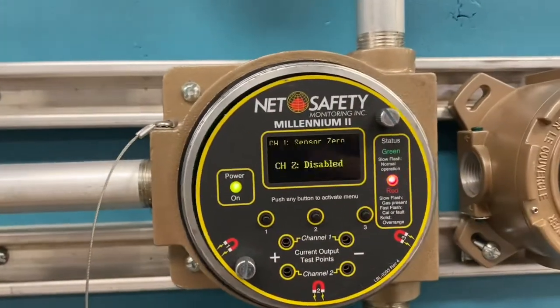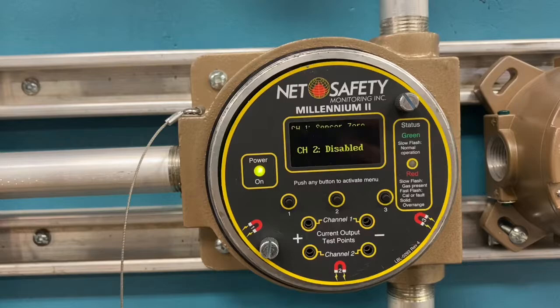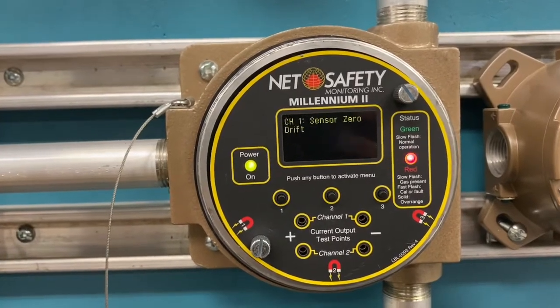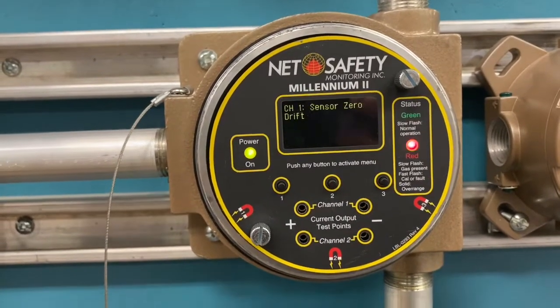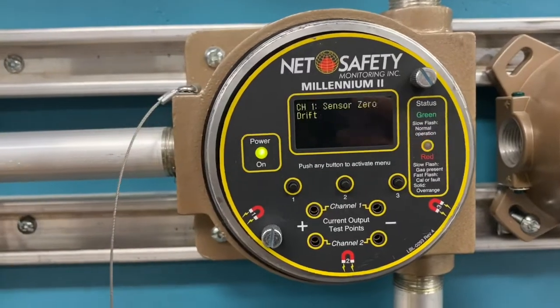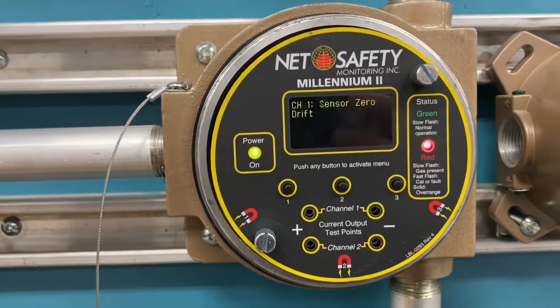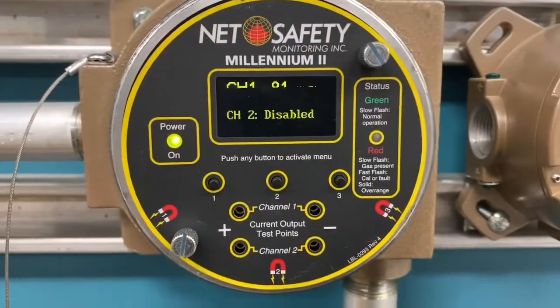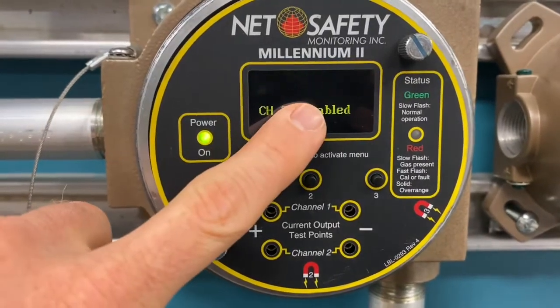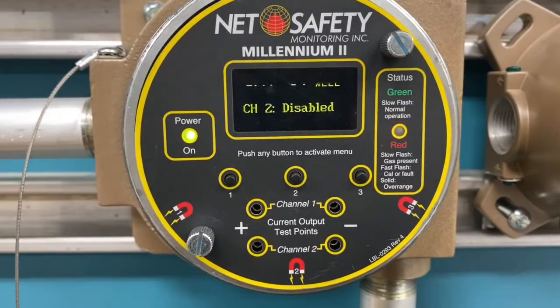What I'm going to do now is apply some zero air just to confirm and see if it doesn't clear our sensor zero drift, and then we're going to apply some calibration gas to see what that does here. But we may just have to calibrate it to get rid of this error. All right, so I applied 50% LEL to our sensor, and you can see here that it's reading 91%. So it definitely has drifted.